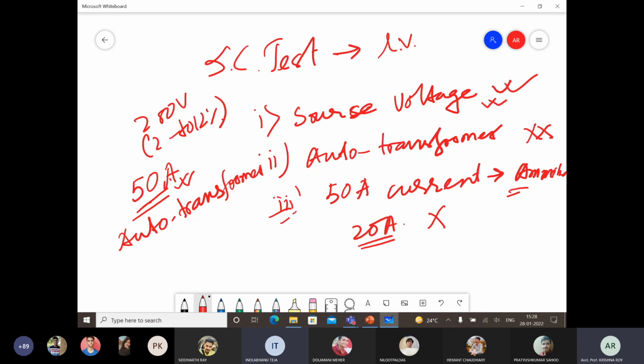In case of high voltage side, we have seen the rated current is 5 ampere only. So 5 ampere can easily be measured. 5 ampere rating auto transformer are easily available, and 2 to 12% of 2000 volt, that is also easily available, isn't it? Yes, sir. So that is why we perform the short circuit test on the high voltage side and not on the low voltage side. Is it clear? Yes, sir. Any question?